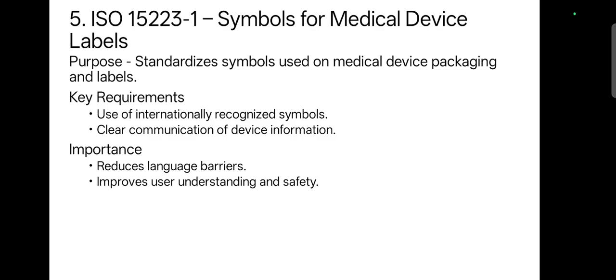The standard provides universally recognized symbols that communicate important information such as expiration date, sterilization method, manufacturer details, storage conditions, and warnings. Using standardized symbols improves communication, reduces label errors, and enhances the safe use of medical devices across different countries.